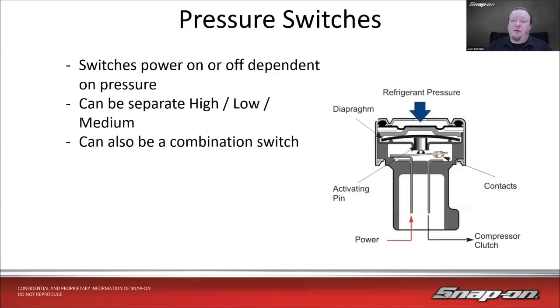Then we also have pressure switches. It's going to power on or off depending on the pressure that's in there. They can be separate high, low and medium switches, or a combination switch with high and low in there. This one's kind of an on-off, so power goes in, and then depending on the pressure, if there's enough pressure in there, the contact will close, and it'll turn the clutch on or off. So those are just kind of dumb switches. Based on pressure, it's going to turn it on and off like a reed switch.